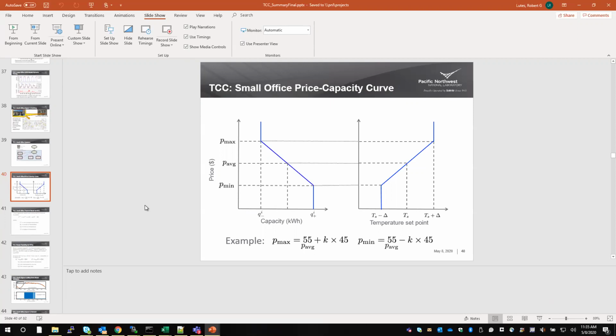Voltron writes at a BACnet priority that's lower than the one used by the operator. So if they controlled that point, they would basically override the Voltron controls, and the controls that they elicited would be used instead of the Voltron controls. And then when the conference was over, they could release that value, and it would re-enter into the regular market service.